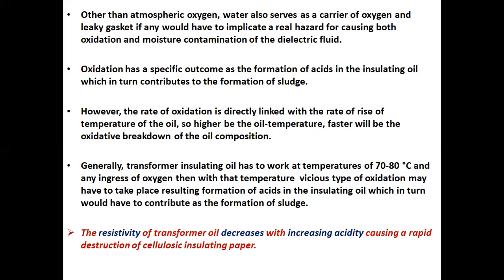The resistivity of transformer oil decreases with increasing acidity, causing a rapid destruction of cellulose insulating paper.